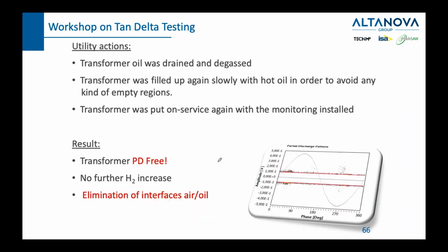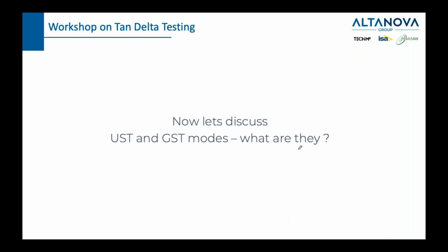What the customer did, they drained and degassed the transformer. It was filled up again with hot oil in order to avoid any kind of empty regions. And the transformer was put in service again with the monitoring also turned on. After that, we saw no more PD. It was just noise. So this concludes, let's say, the second third.